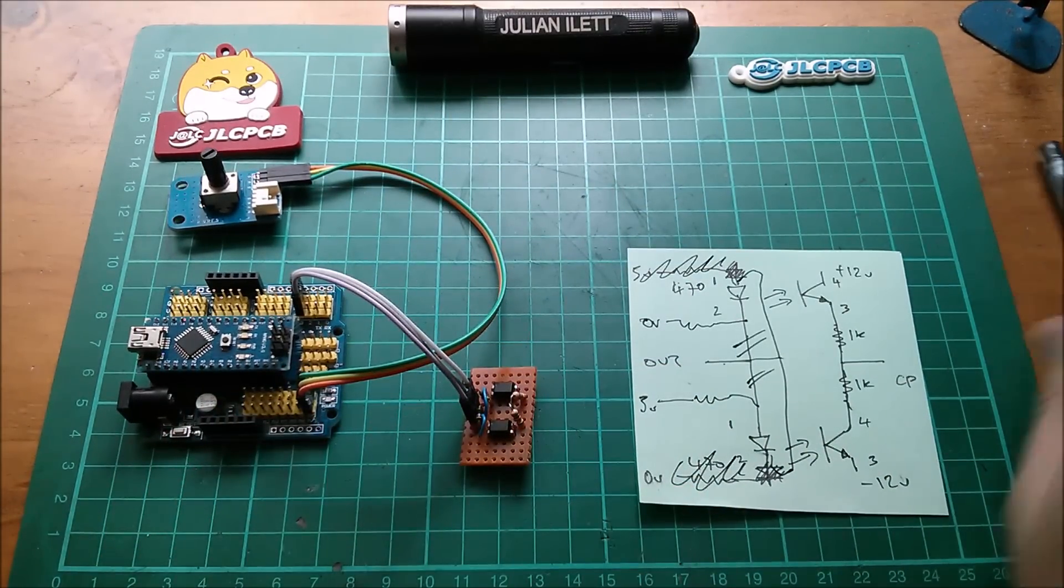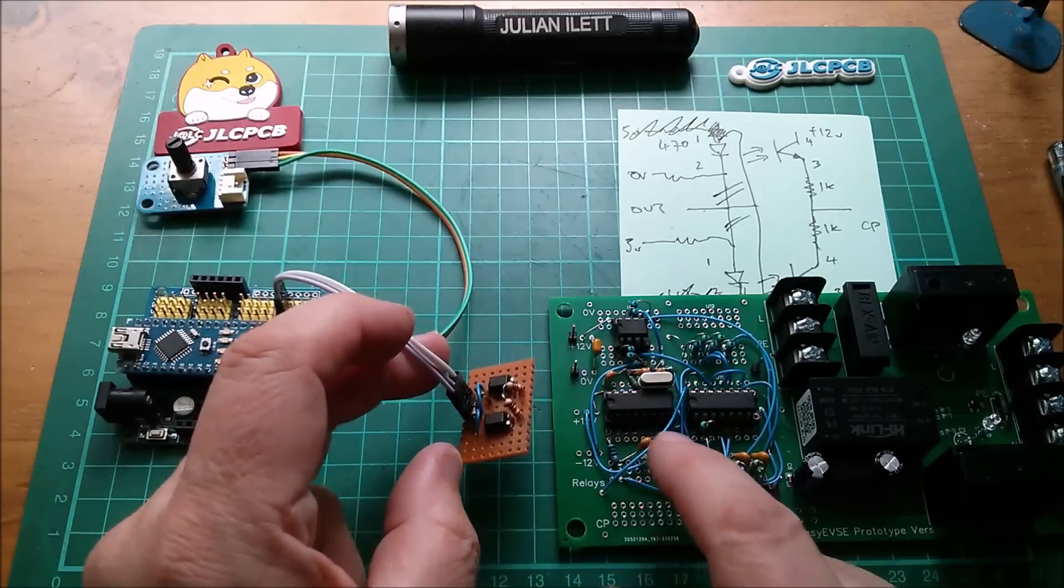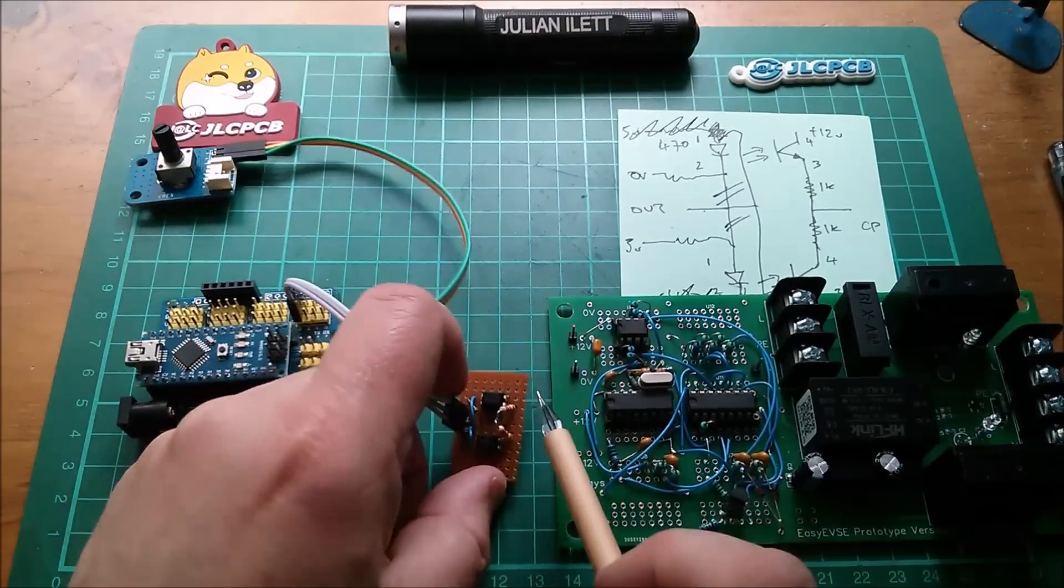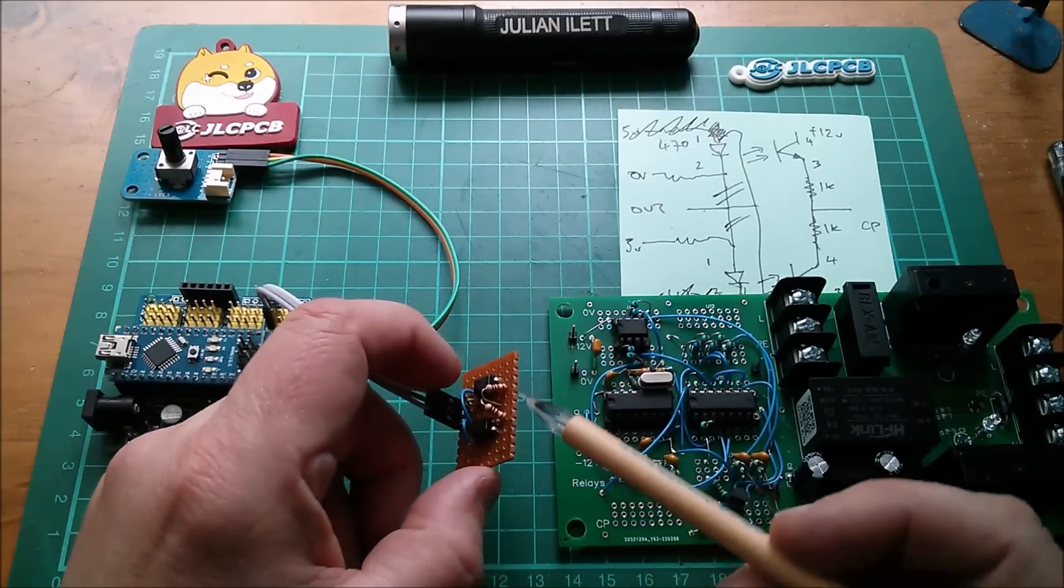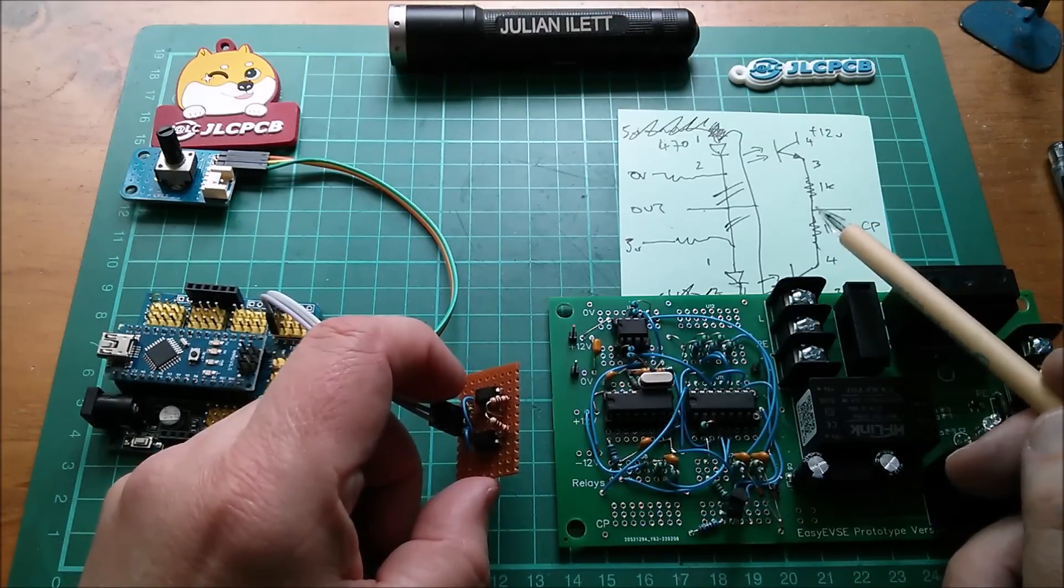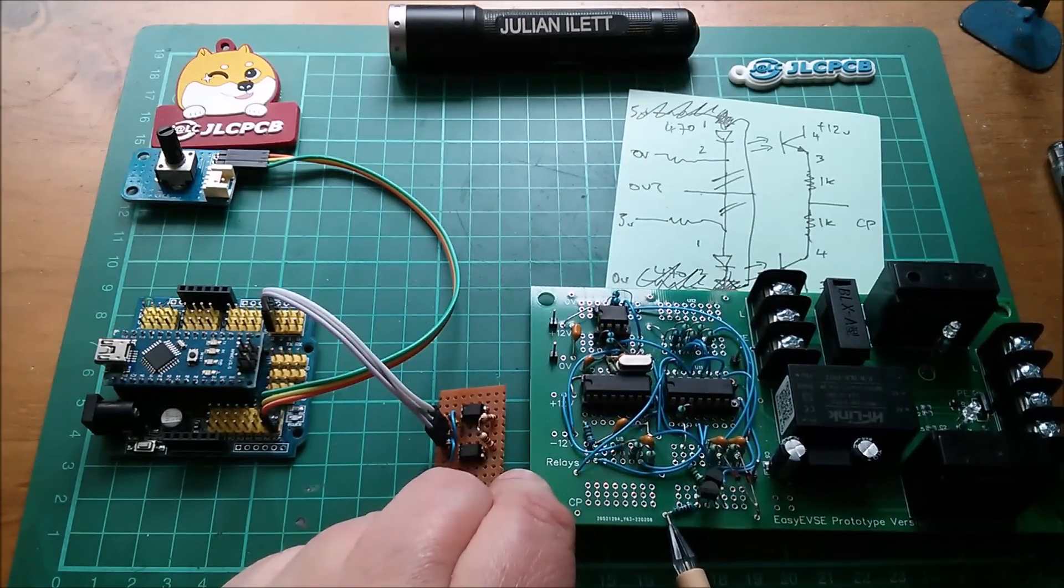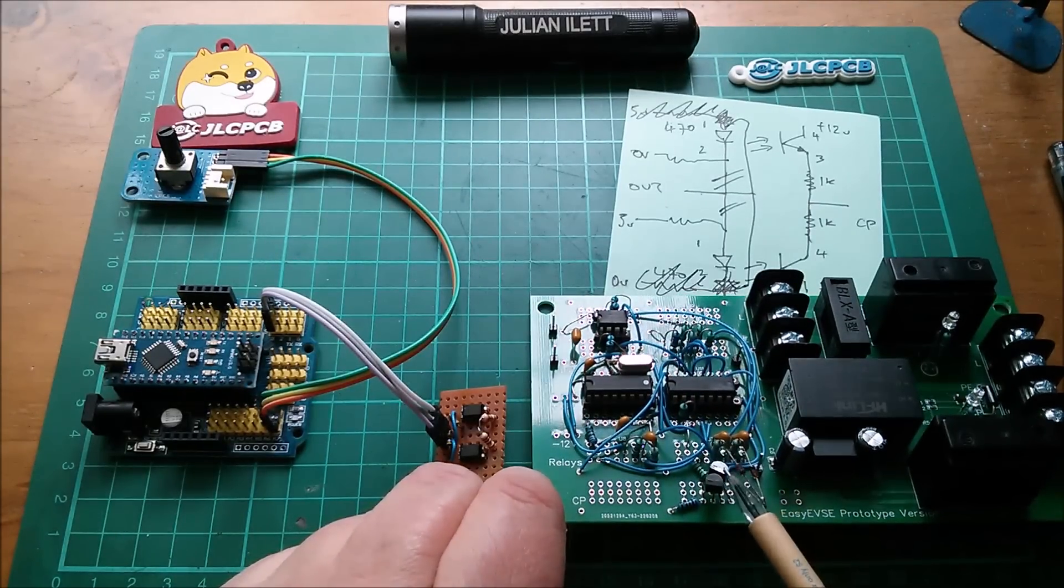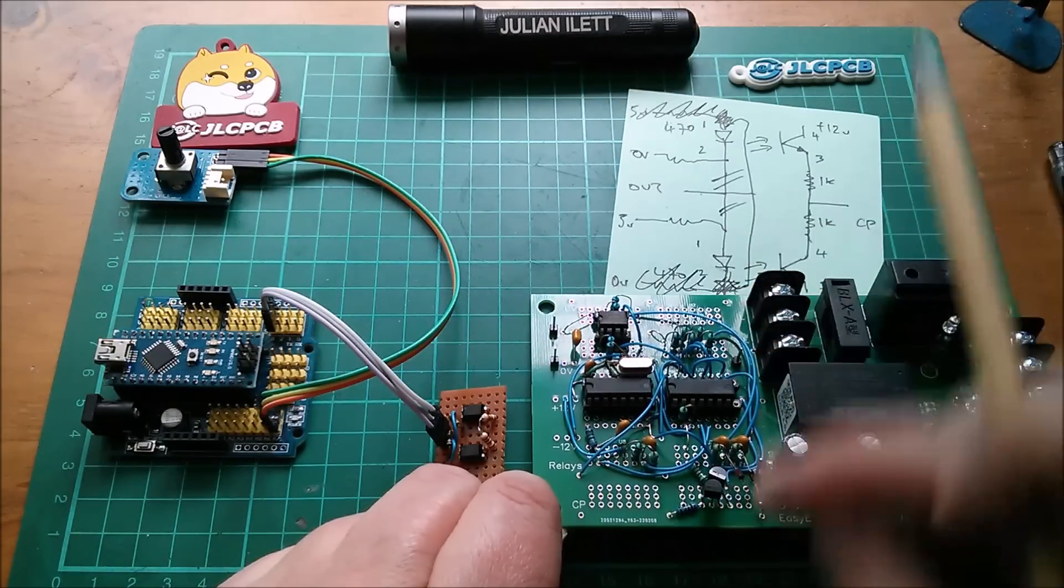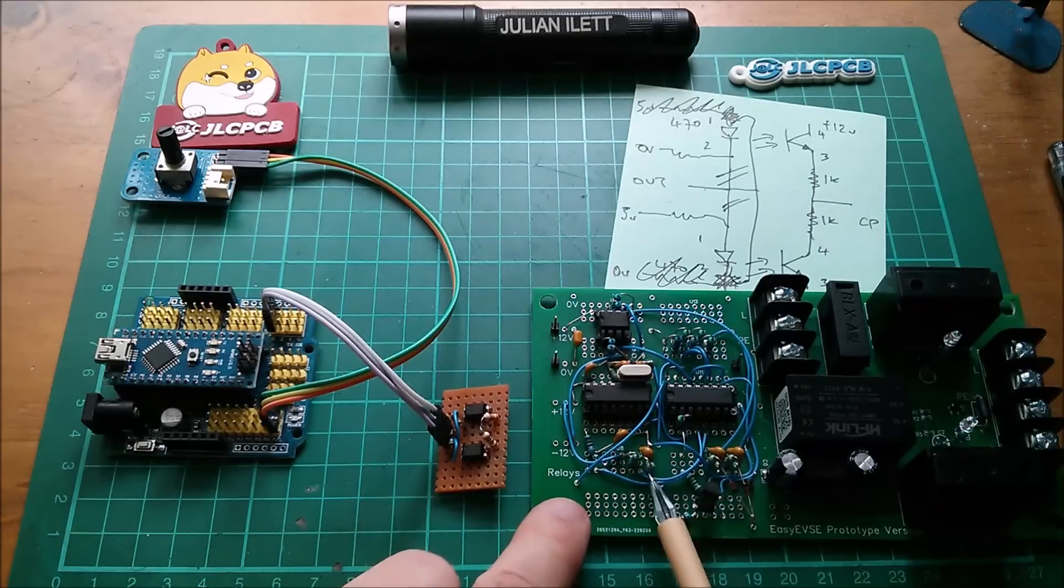So what I need to do now is connect the opto isolator driver to here. Now fortunately we have a plus 12 volts there which goes to this upper opto and minus 12 volts here which goes to the lower one. Then the center point where these two resistors meet will connect through to CP. Then all I need to do is cut the 1k resistor that came from my previous line driver for the CP line, which was these two transistors working as emitter followers in a push-pull arrangement. So I'll just cut that resistor and solder this new driver onto this board.